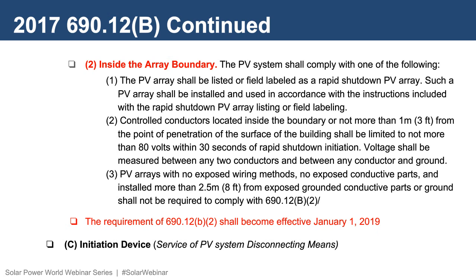The requirements of 690.12(B)(2) will not become effective until January 1st, 2019. This allows for the industry to catch up with the code by manufacturing listed equipment, as well as to develop product safety standards for rapid shutdown arrays. The 2017 version of rapid shutdown also introduces the requirement for a rapid shutdown initiation device. This device must consist of one of the following: a service disconnecting means, a PV system disconnecting means, or a readily accessible switch.